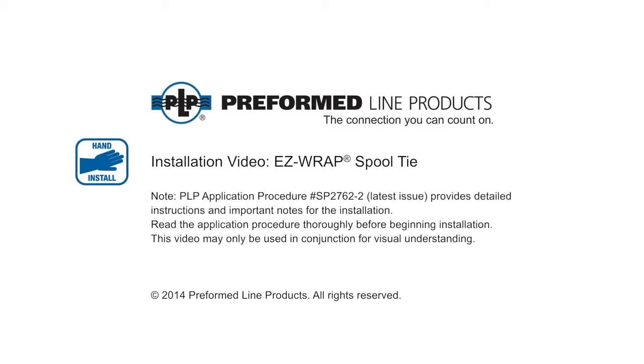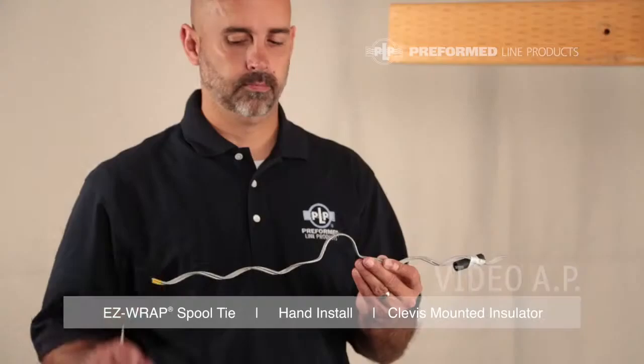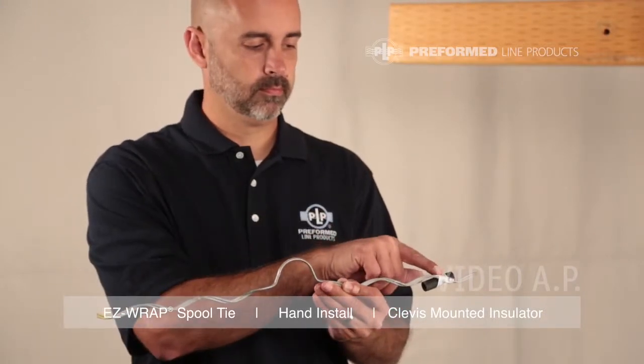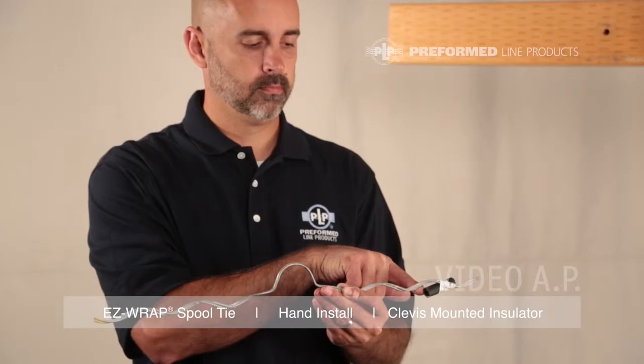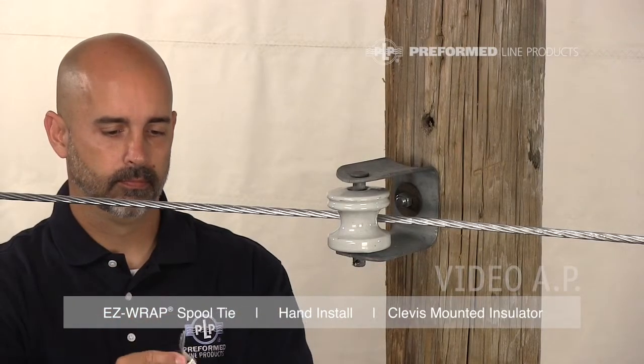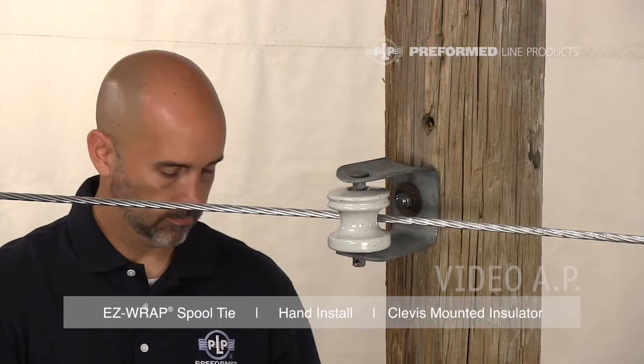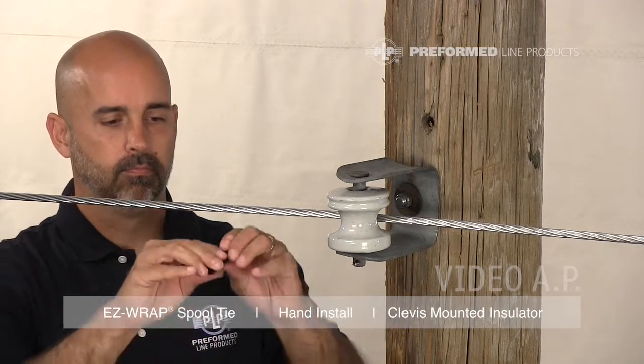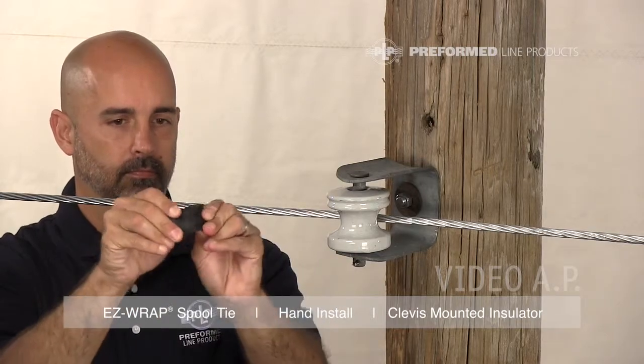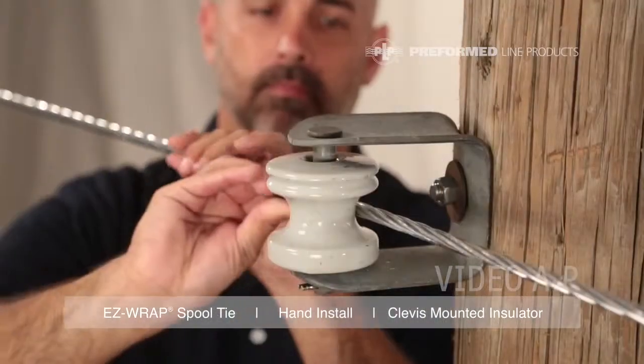Welcome to Preformed Line Products. The following presentation illustrates the recommended hand application of the EZ-WRAP Spool Tie. Remove the tie tube from the tie and install it on the conductor. Open the tube at the split and fold it back on itself several times to reduce stiffness, using the other half as a handle.